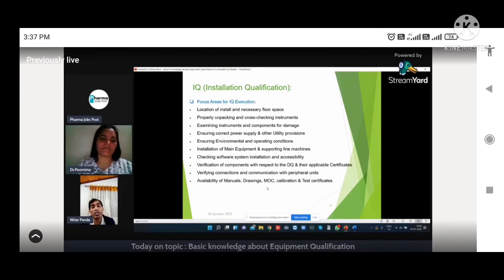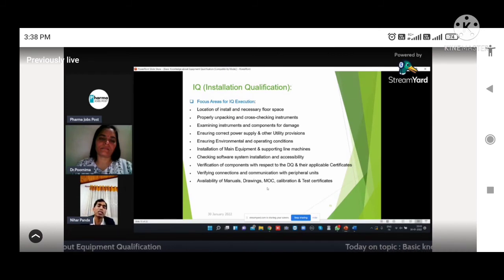We have to check the feasibility of working space and alignments, all the things need to be verified. Not only for the main equipment, but also for the line equipment, you have to check and ensure. Next, verifying the connectivity, connections and communications with peripheral units. Peripheral units means maybe the server, maybe the line machines, maybe the equipment printers and other components also. We have to check whether proper connectivity is there or not. All the things need to be verified during the installation qualification.